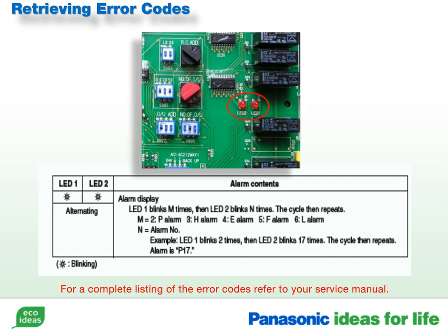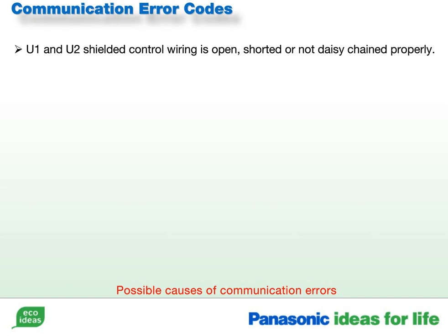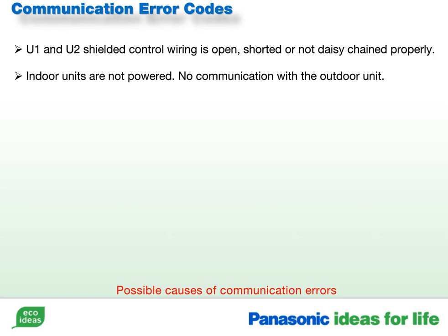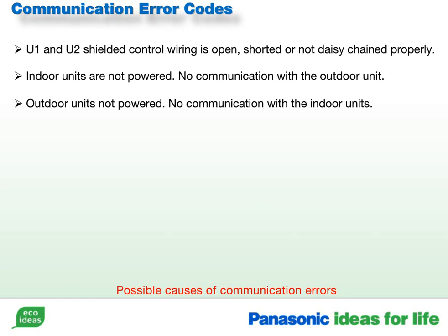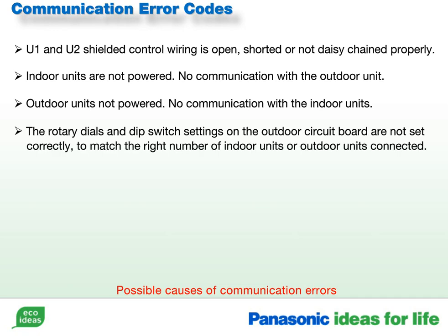When you are commissioning an ECOi system, the most common error codes you may encounter are communication errors. These error codes begin with the letter E. Some of the probable causes of communication errors are as follows. The U1 and U2 control wiring is open, shorted or not properly daisy-chained. An indoor unit or units do not have power and cannot communicate with the outdoor unit. The outdoor unit does not have power, and they cannot communicate with the indoor unit. The rotary dials or the dip switches on the main PCB have not been set correctly, and do not match the number of indoor or outdoor units connected.